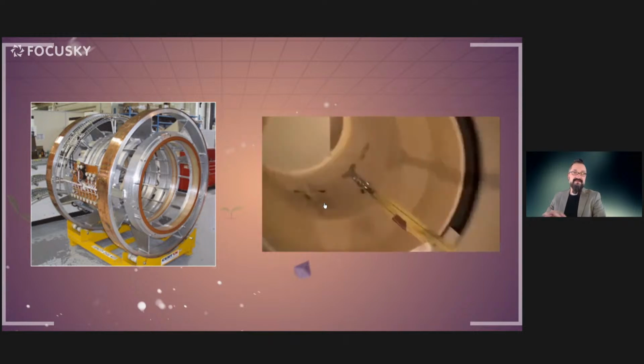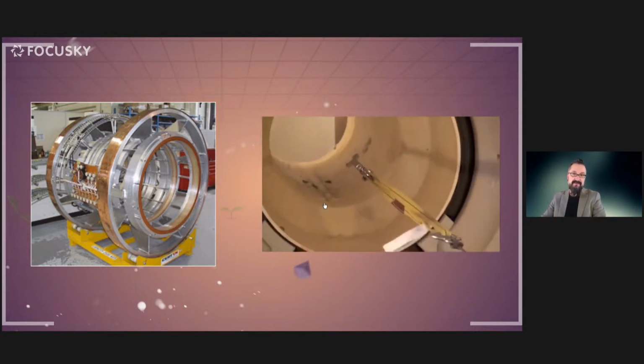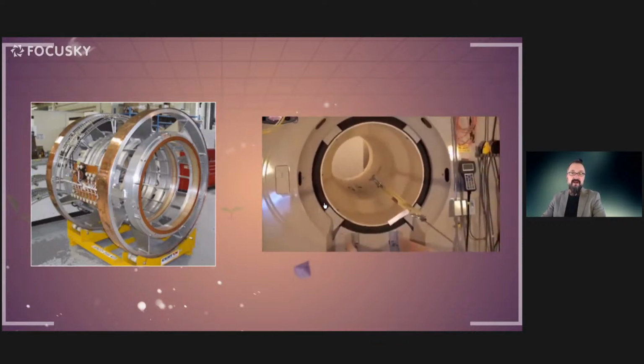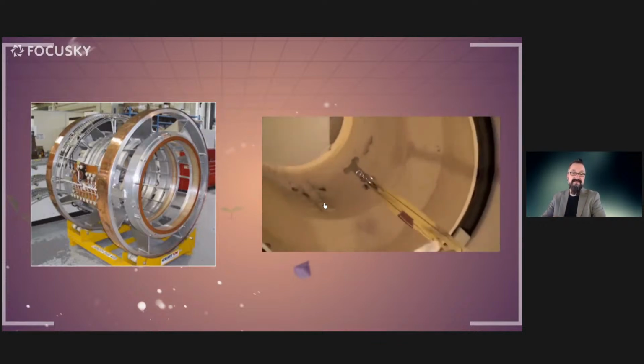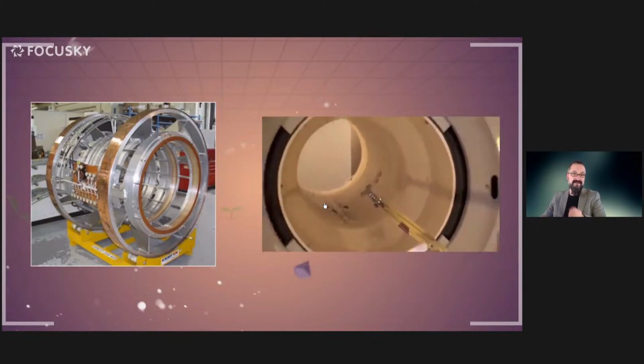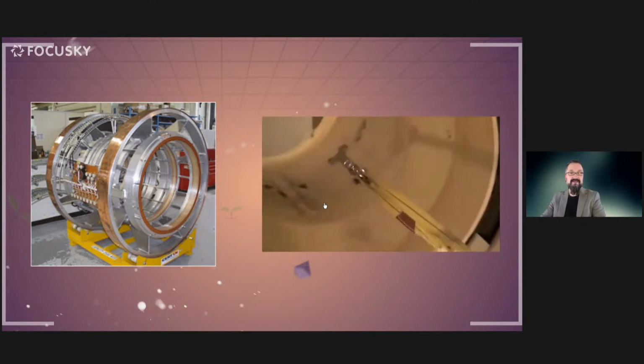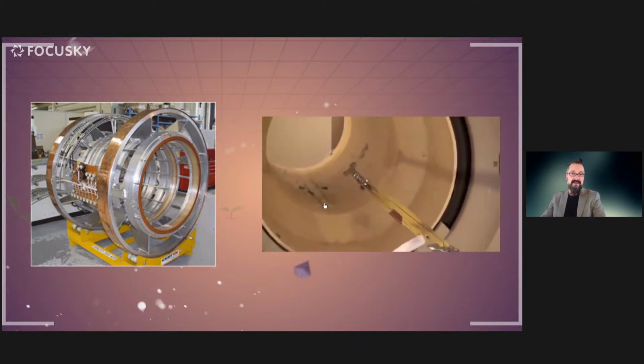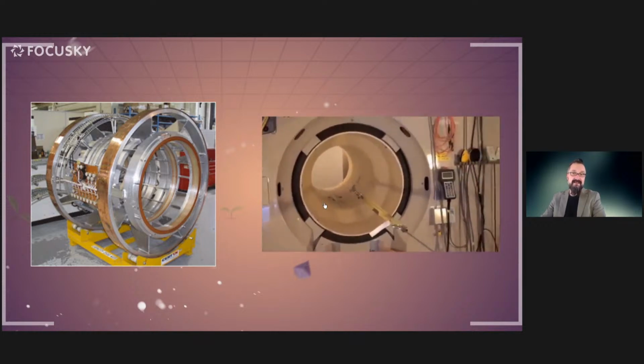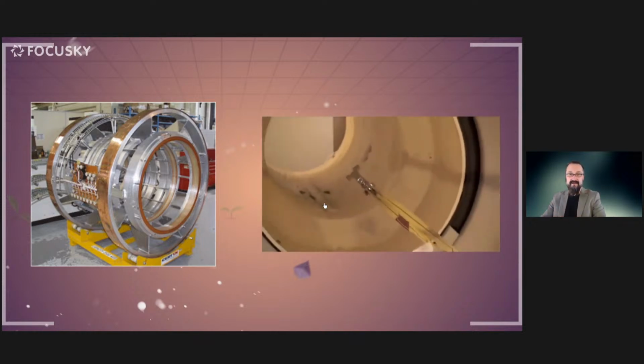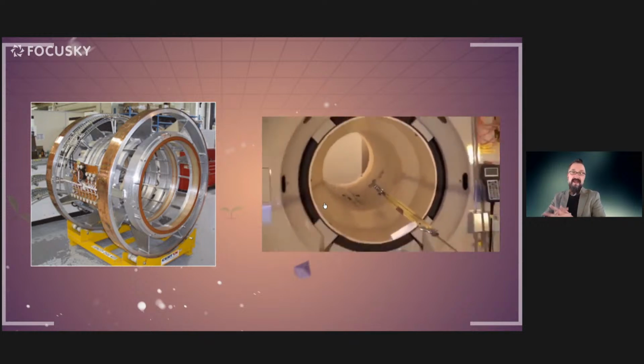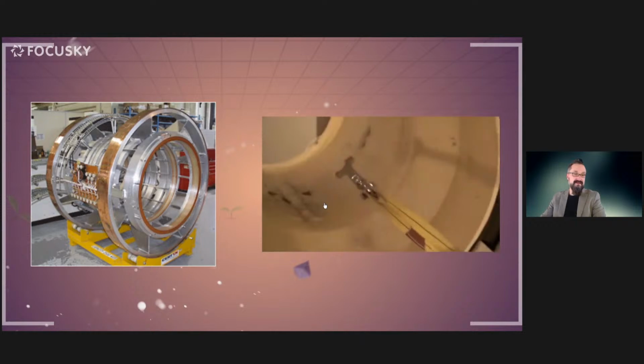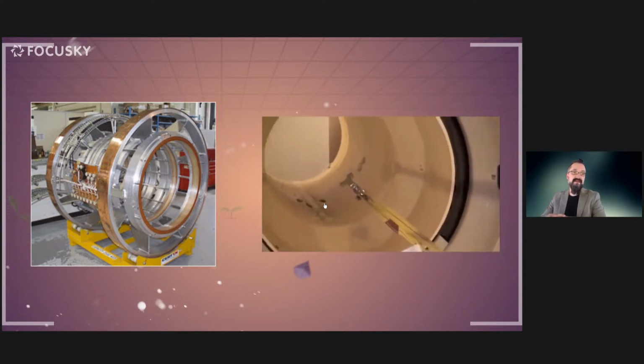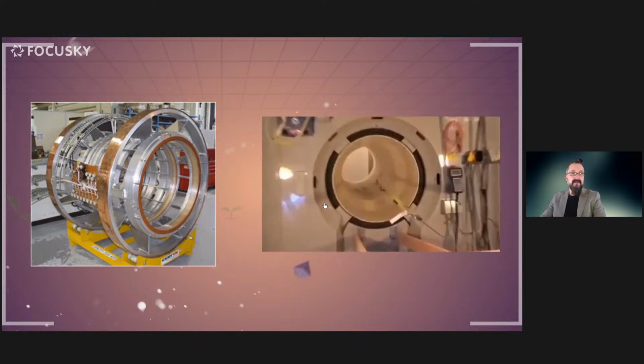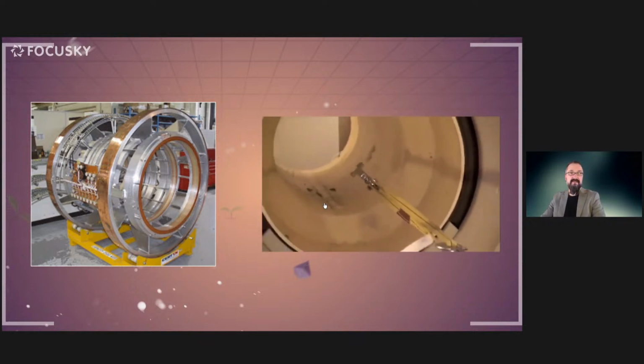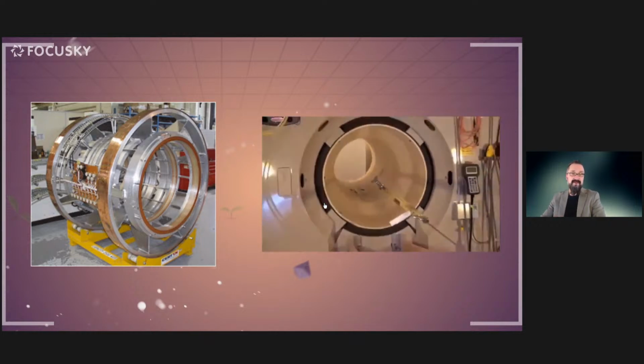And what this Tesla strength means, you can see here in this short clip, because this is a wrench and it's only held in place by an industrial fixture, because if it wouldn't be held in place, it would fly right into the scanner and do a lot of destruction. And this is why you are not allowed to take any metal with you when you enter an MRI scanning room, because this metal would fly out of your hand and into the scanner. And this is also why it's important for a patient not to have any implants in the body that react to magnetic fields, because those implants could heat up, and the patient could be hurt by this.